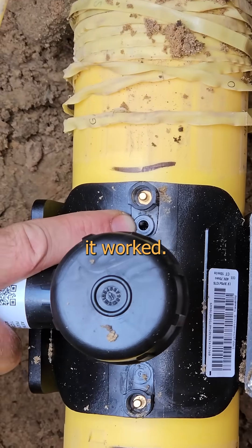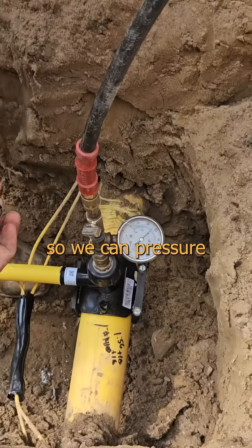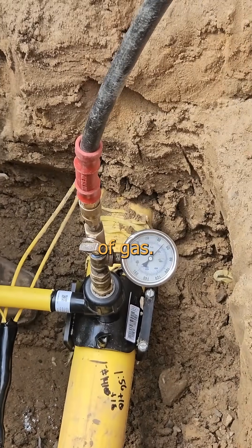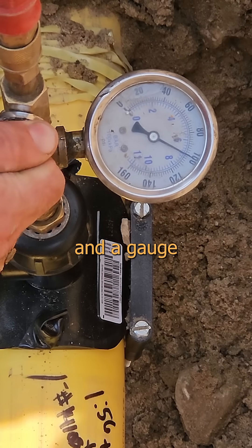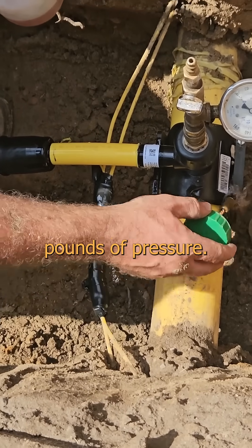The little pop-up timer tells us that it worked. Even though it's permanently attached, there's still no hole in the pipe, so we can pressure test it with no danger of gas. For that, we connect a little valve and a gauge to the air compressor and fill it up with about 100 pounds of air. The gas will only be at a couple pounds of pressure, so the safety factor here is better than a climbing harness.